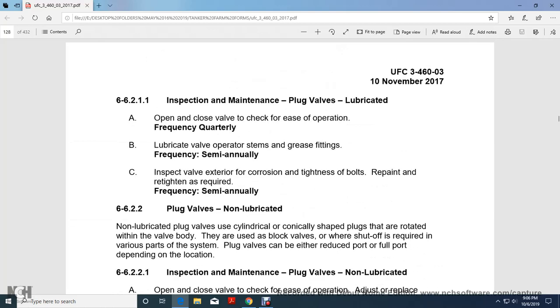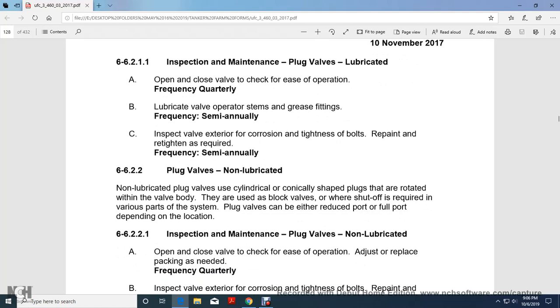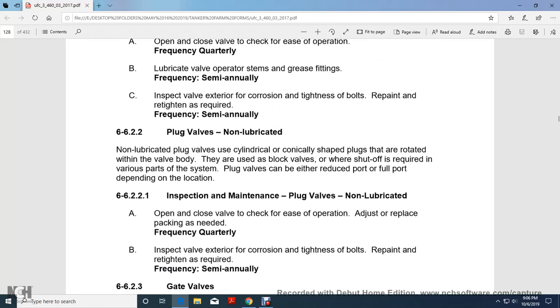6-6.2.1.1, inspection and maintenance of lubricated plug valves. Open and close the valve to check for ease of operation quarterly, and lubricate the valve operator, stems, and grease fittings semi-annually. Inspect for exterior corrosion and tightness of the bolts, and repaint and retighten as required, semi-annually. Non-lubricated plug valves: cylindrical shaped plugs are rotated within the valve body. The valves are used where shut off is required in the various parts of the system.